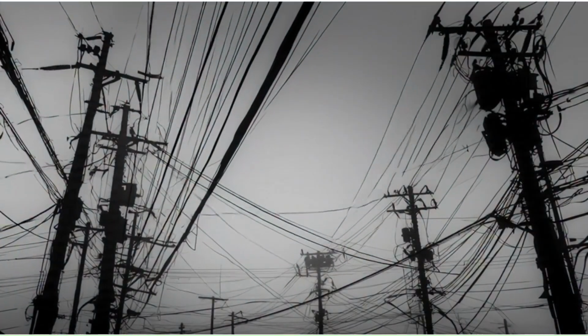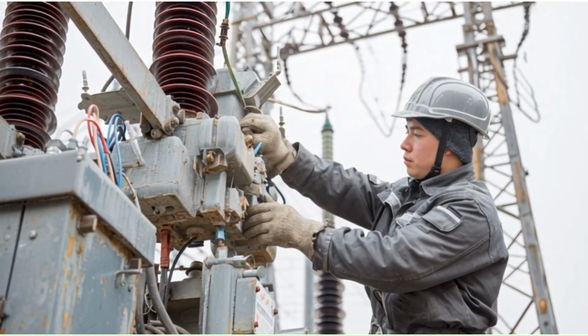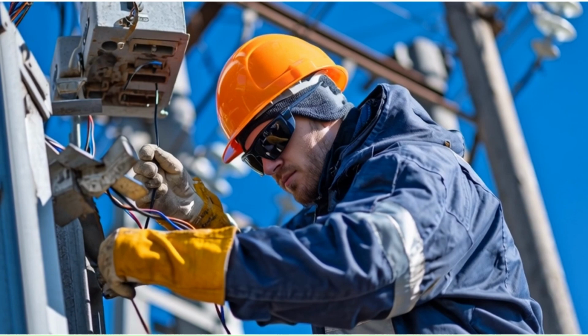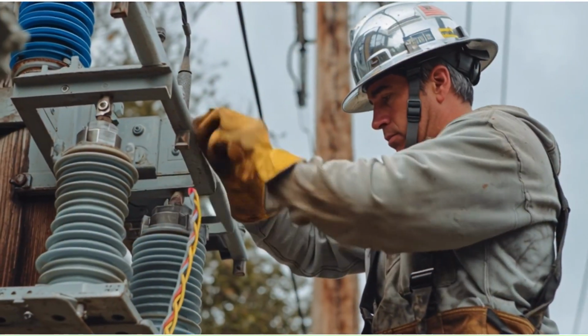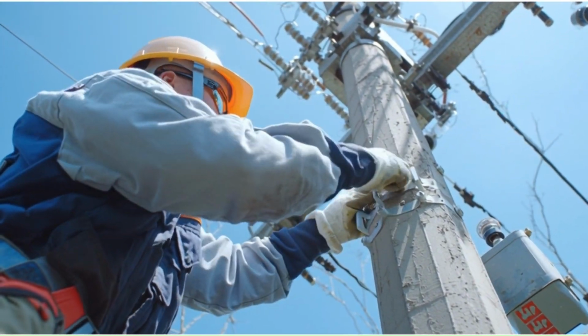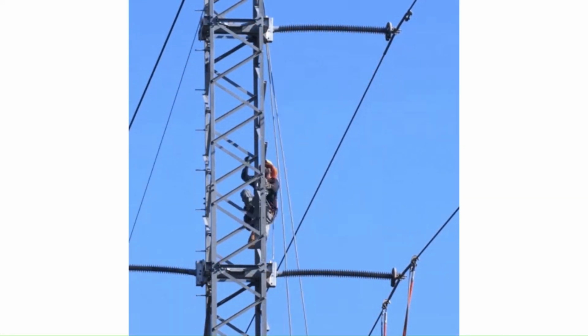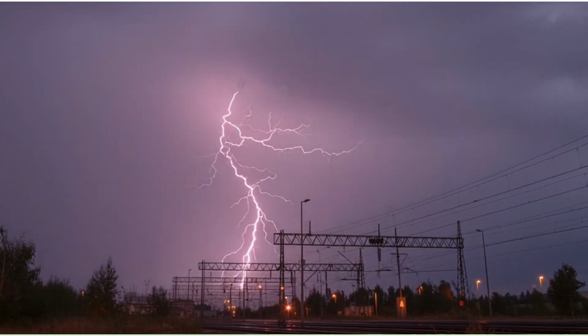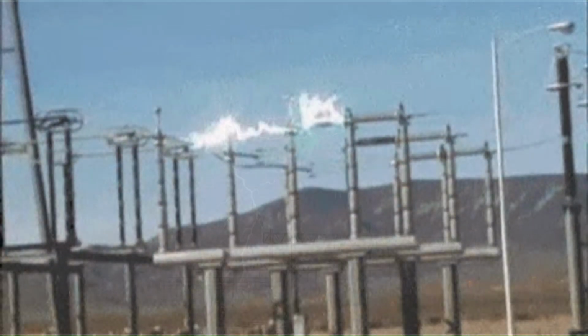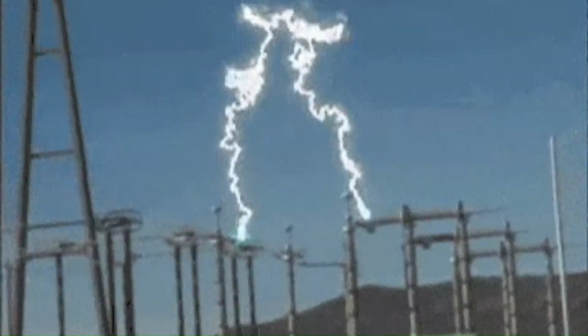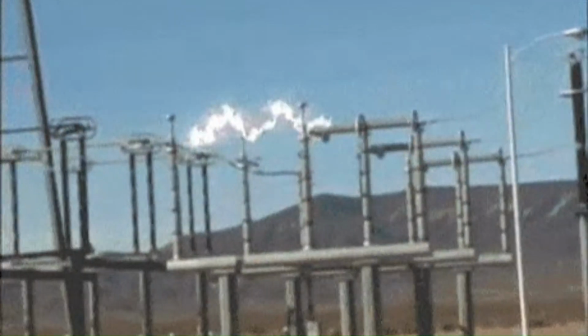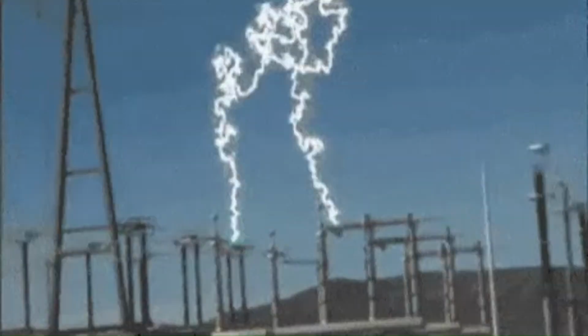High winds can cause power line conductors to swing and touch each other. Also, utility actions like switching capacitor banks or changing a transformer tap can create temporary voltage fluctuations, which are also a type of transient fault. A permanent fault is a long-lasting issue that requires a physical repair, unlike a transient fault, which is for a short duration of time. For example, a lightning strike can cause a permanent failure of a transmission line, a short circuit to the ground or between phases, or a broken insulator string, which is also an example of a permanent fault.